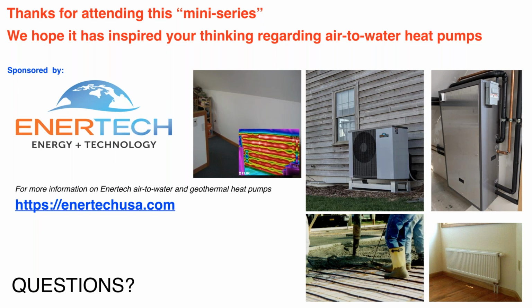Okay, the next question is, and this looks like the last question, do the variable speed pumps turn off when there is no demand call? No. Well, it does depend. It depends on how they're wired. For example, if you're doing a hydronic system and you're using a multi-zone relay panel, and they're available from a lot of different companies today, and you're using zone valves, you could set the circulator up so that if all the zone valves are closed, it de-energizes. If you're using thermostatic valves on panel radiators, there's no electrical feedback from those valves. So in a case like that, if the pump detects that all the thermostatic valves are closed, it goes into what I call a sleep mode.